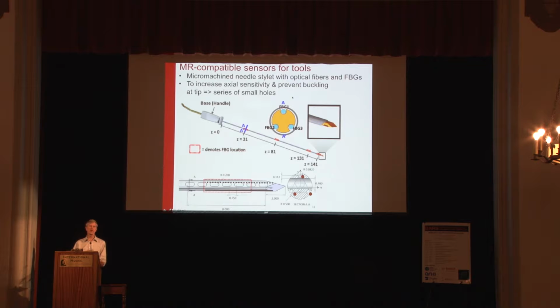So we've been working with optically instrumented tools. These are optical fibers. You micromachine grooves in the inner stylet of a needle. You have fiber Bragg gratings. They're very accurate optical strain gauges. And then we micromachine little holes at the tip of the needle. That gives us a better sensitivity to axial forces as well as bending.